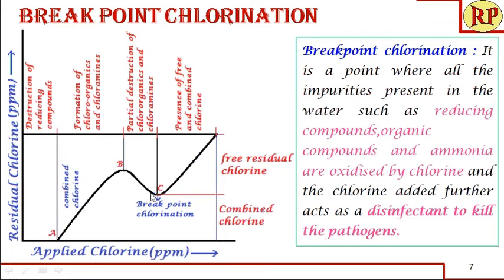Not all chloro-organics and chloramines are removed — they are only partially destroyed, so the graph curve does not come all the way down. This part is the combined chlorine and the other part is the free residual chlorine. The total residual chlorine is the sum of both. You can determine the combined chlorine by subtracting free residual chlorine from total residual chlorine. Chloramines also act as disinfectants, but their disinfection power is 40 to 60 times less than that of free residual chlorine.